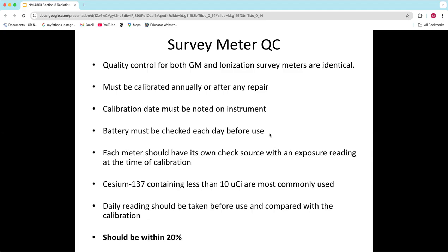Battery has to be checked daily. So typically on your meter, you're going to have a switch or a button that you can push, and then it will give you a reading on your meter based on the battery. Obviously, you have to make sure you have good batteries in your meters, because if you don't have batteries, you're not going to get voltage. If you don't get voltage, then that ionization reaction can't occur. So conceivably, you could think you were measuring, and if your batteries are weak or whatever, that could potentially mess with your voltage and you're not getting accurate readings. So usually there's again a button to check your battery. That is a daily check that should happen.